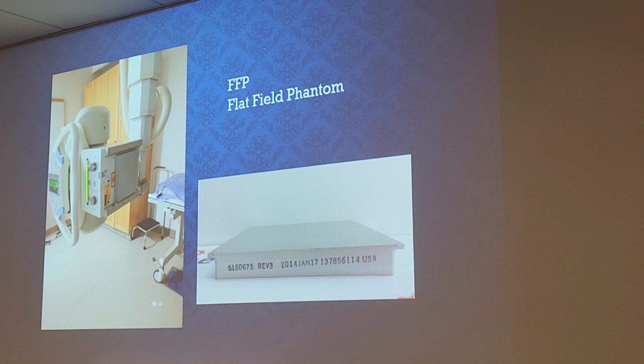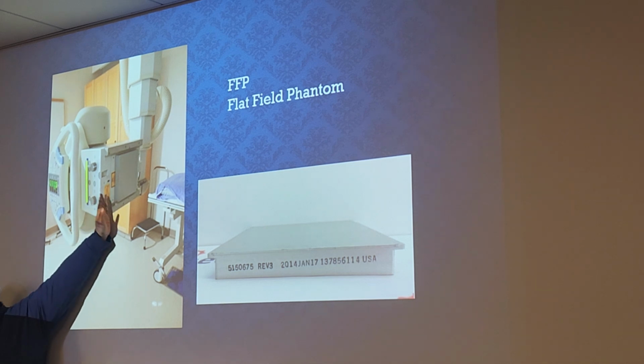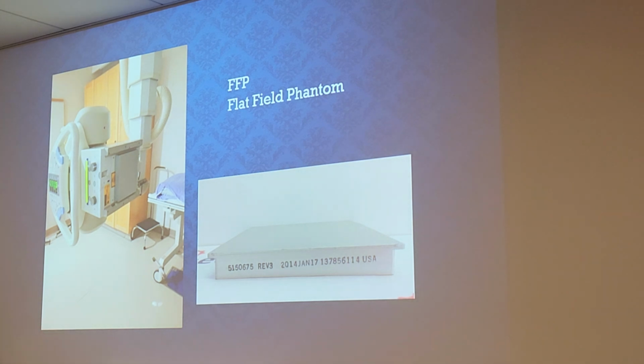You'll just slot it there at the bottom of the collimator, and you expose the entire IR. We've talked about flat fields before: flat field correction, exactly. So how do you test for flat fields? You would use this flat field phantom to do your corrections and your calibrations. This flat part is the part that's closest to the tube, the part you're sliding. That's why they call it flat.